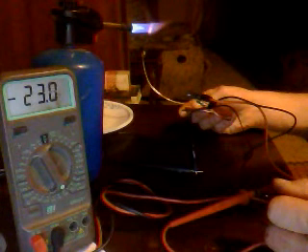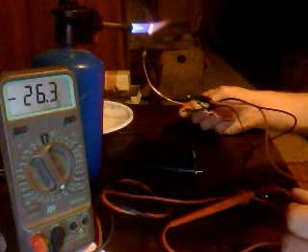You want this thing to at least get around 24 millivolts and it's good — it'll work. This is a good thermocouple; there's nothing wrong with it. So if the pilot wasn't staying lit, and you pushed in the button, kept the pilot on the thermocouple, and tested 24 millivolts down at the meter end, then your problem is the gas valve or there's another issue.